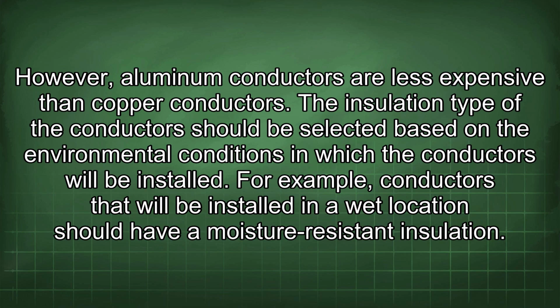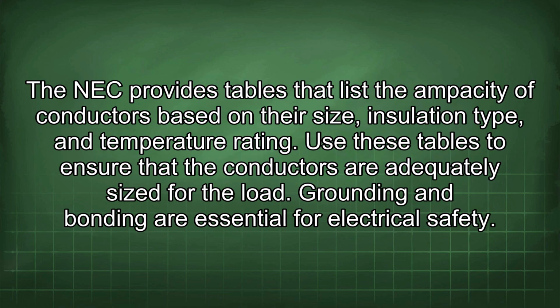The insulation type of the conductors should be selected based on the environmental conditions in which the conductors will be installed. For example, conductors that will be installed in a wet location should have a moisture-resistant insulation. The NEC provides tables that list the ampacity of conductors based on their size, insulation type, and temperature rating. Use these tables to ensure that the conductors are adequately sized for the load.